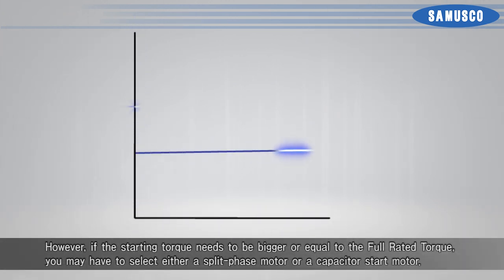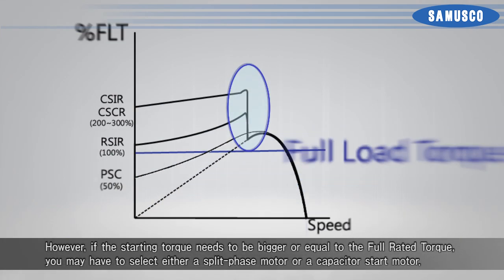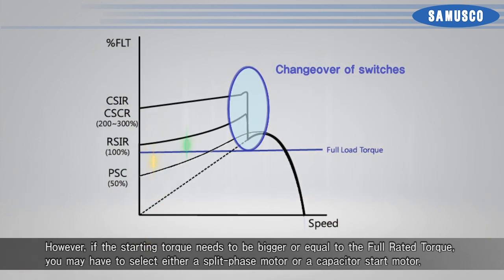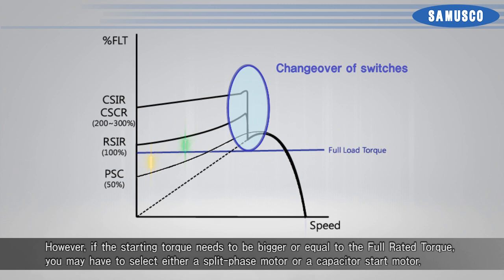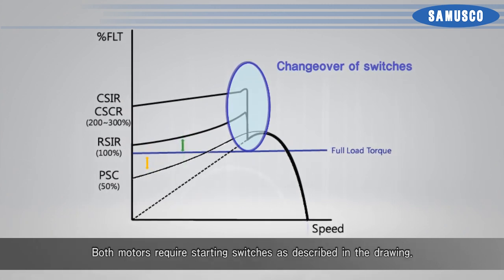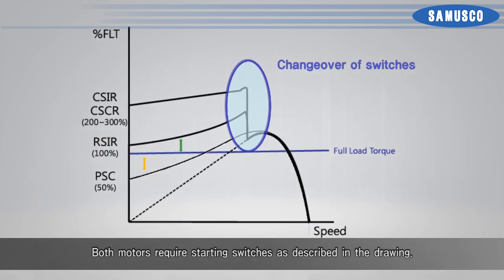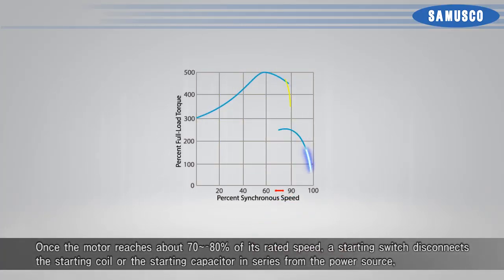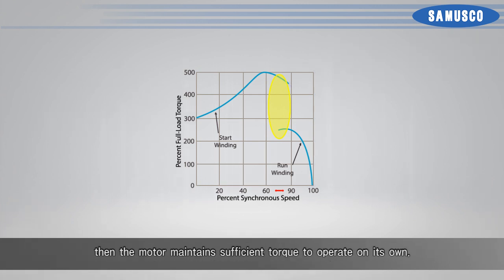However, if the starting torque needs to be bigger than or equal to the full rated torque, you may have to select either a split-phase motor or a capacitor start motor. Both motors require starting switches as described in the drawing. Once the motor reaches about 70 to 80% of its rated speed, a starting switch disconnects the starting coil or the starting capacitor in series from the power source. Then the motor maintains sufficient torque to operate on its own.